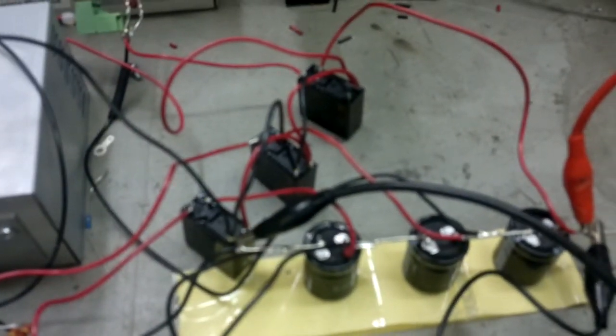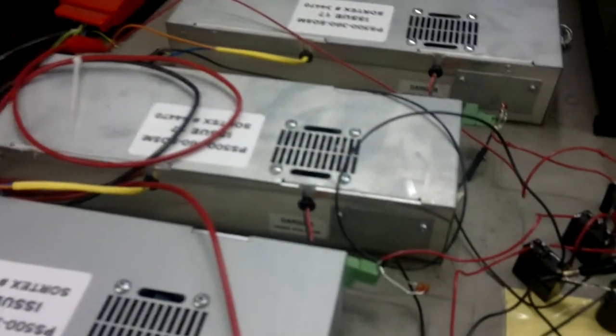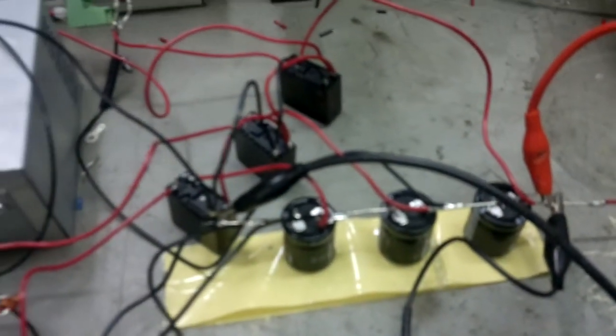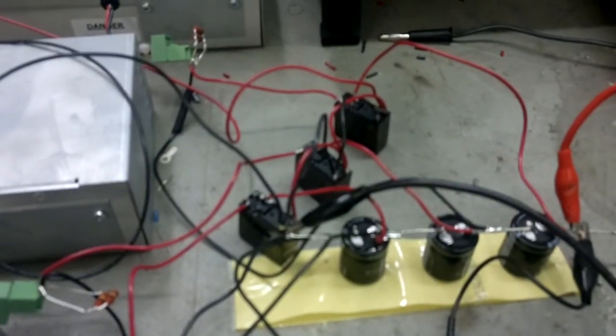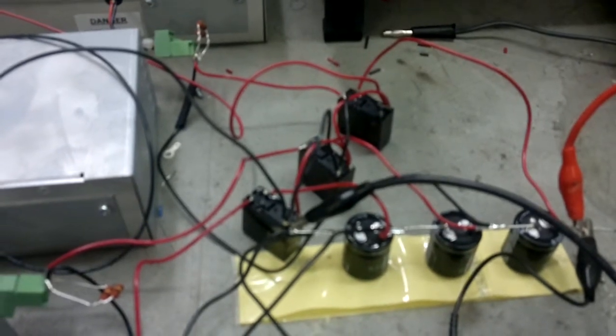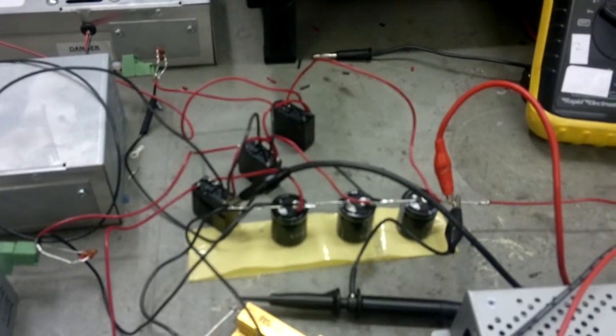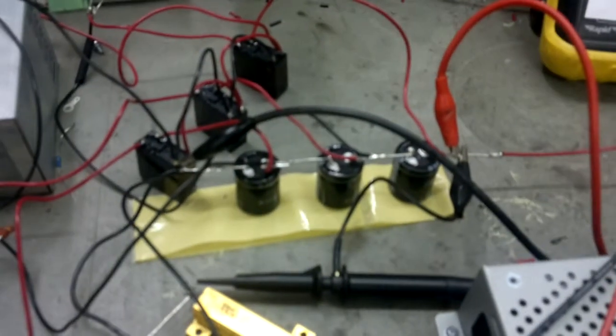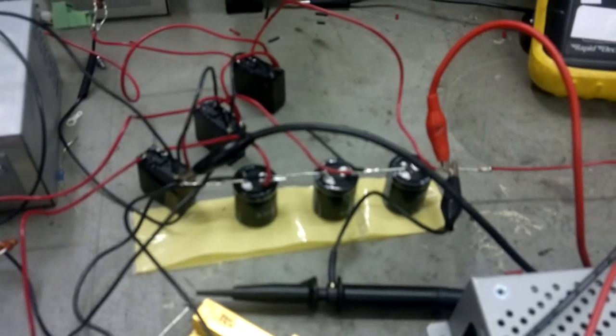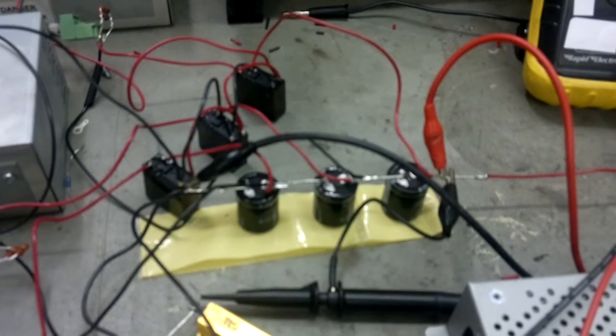Those relays are connected so that when the energy pulse from the capacitors is discharged into the DC to DC converter, which is here, the power source, the three power supplies that are charging the capacitors, can be disconnected from each other, so that as the energy is taken from the capacitor bank, the power supplies don't keep pumping energy into the capacitors, which would prolong the duration of the test. So the capacitor value is set to give the 1 or 2 milliseconds time period for the minus 1100 volts.